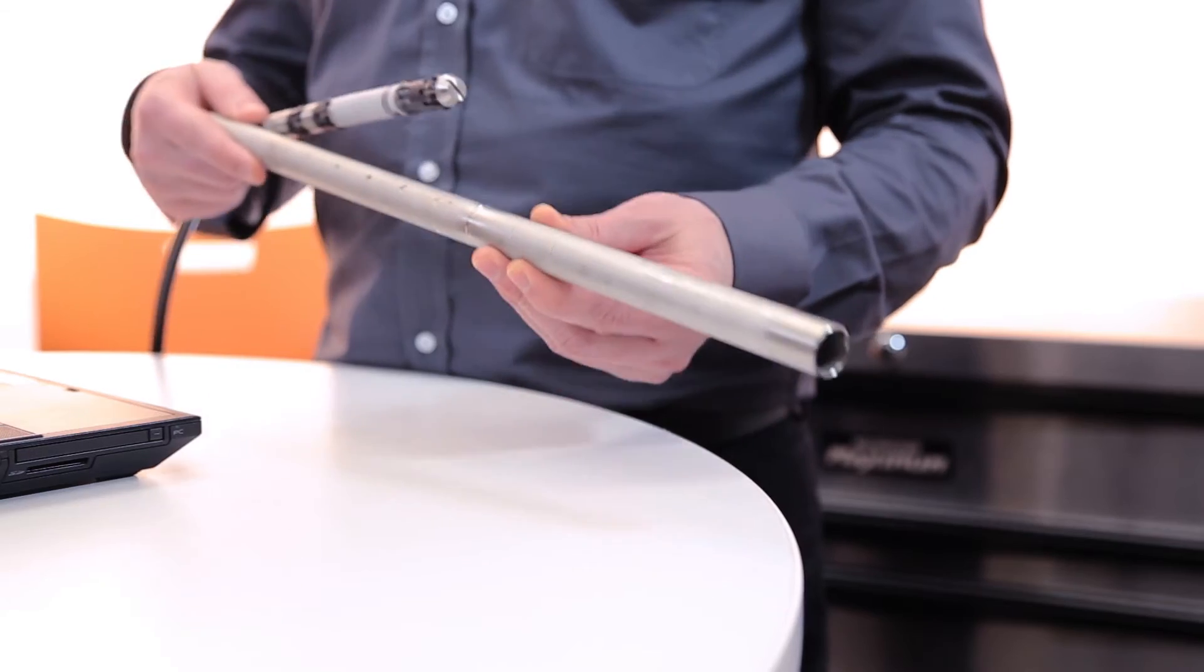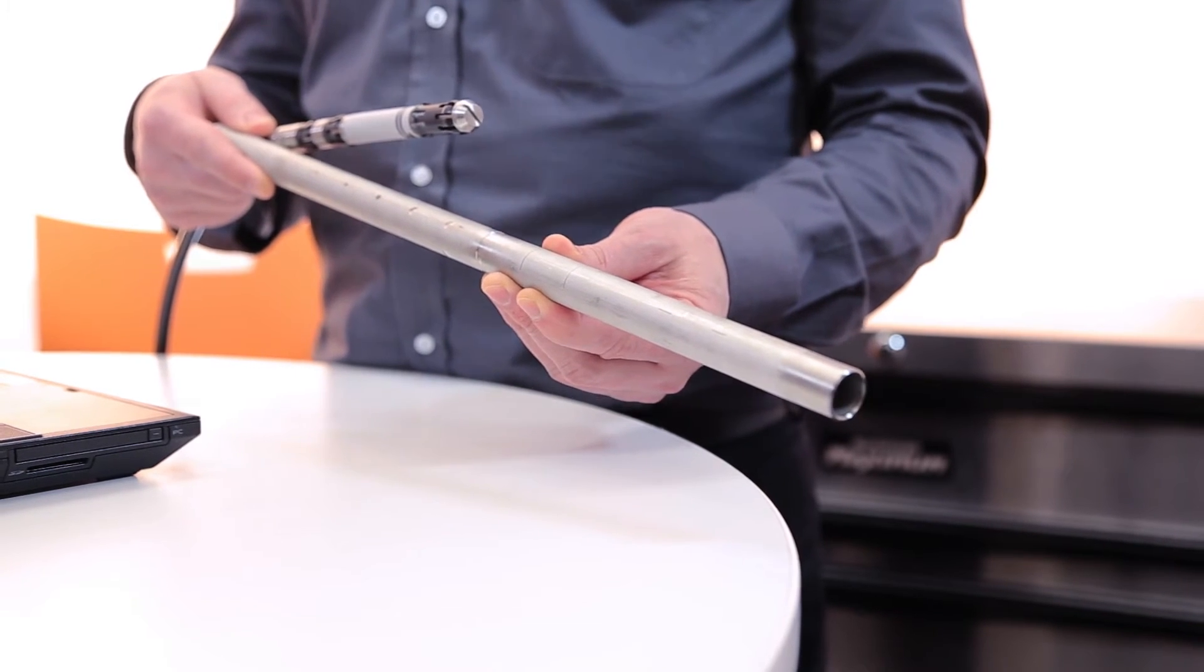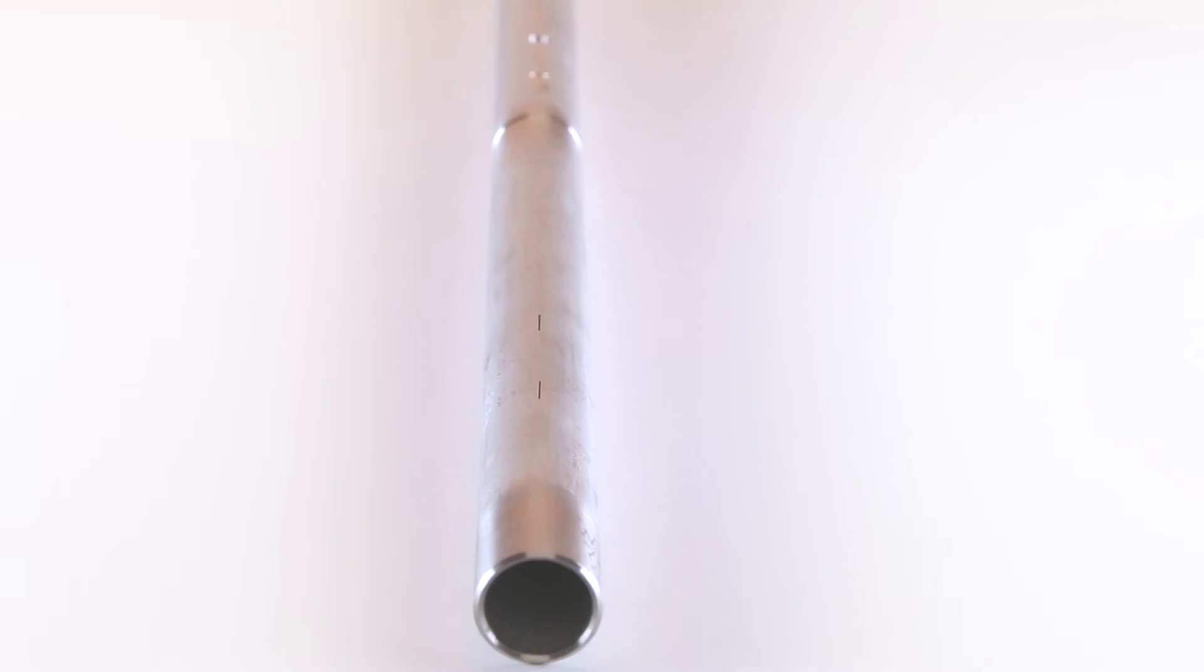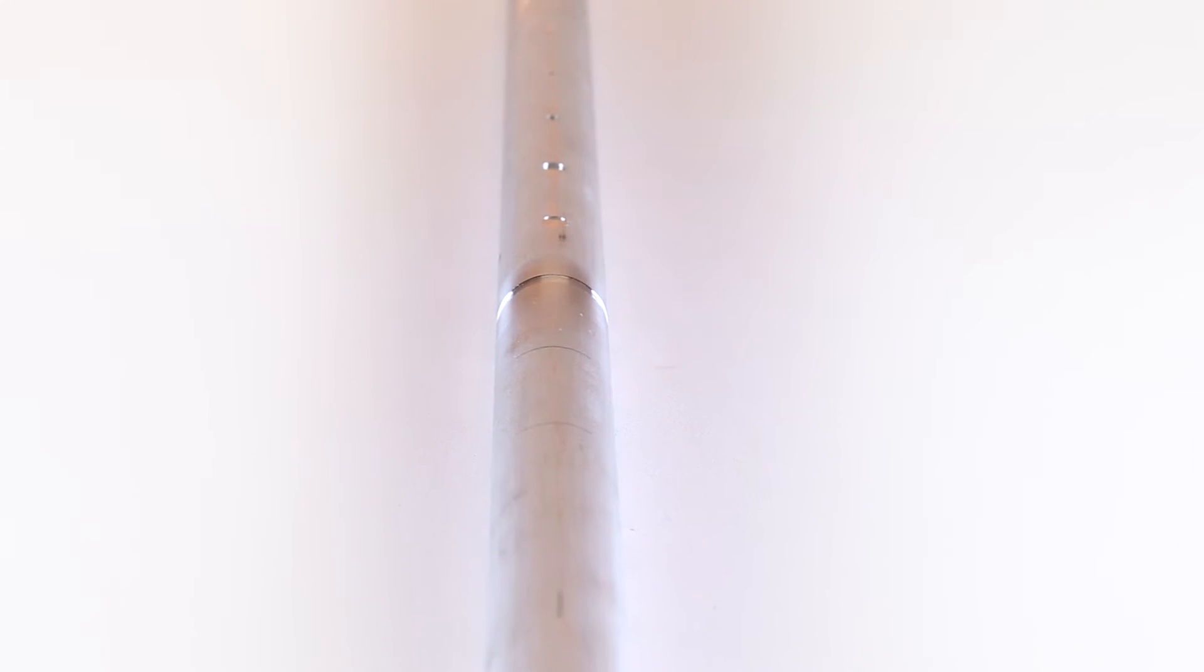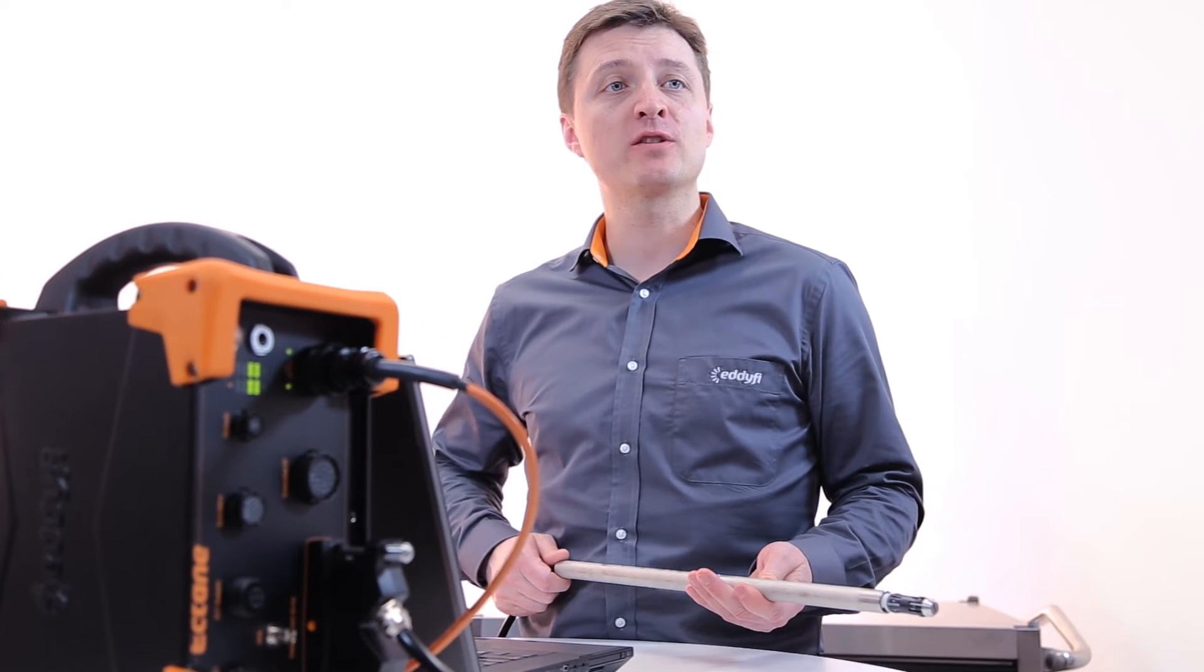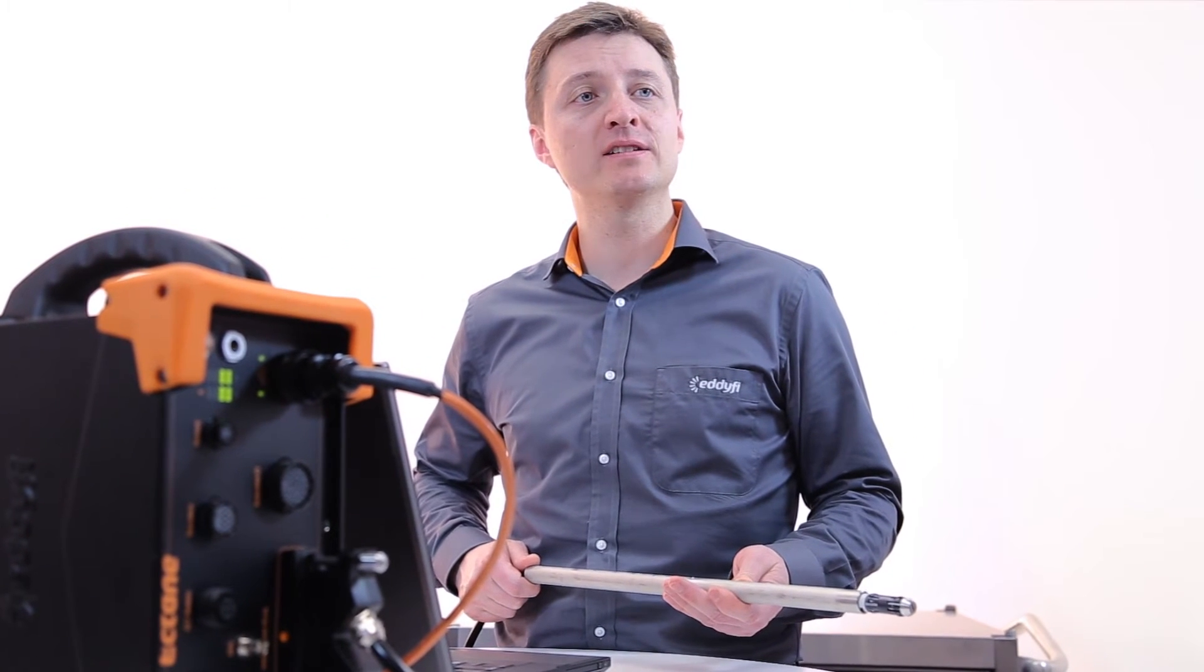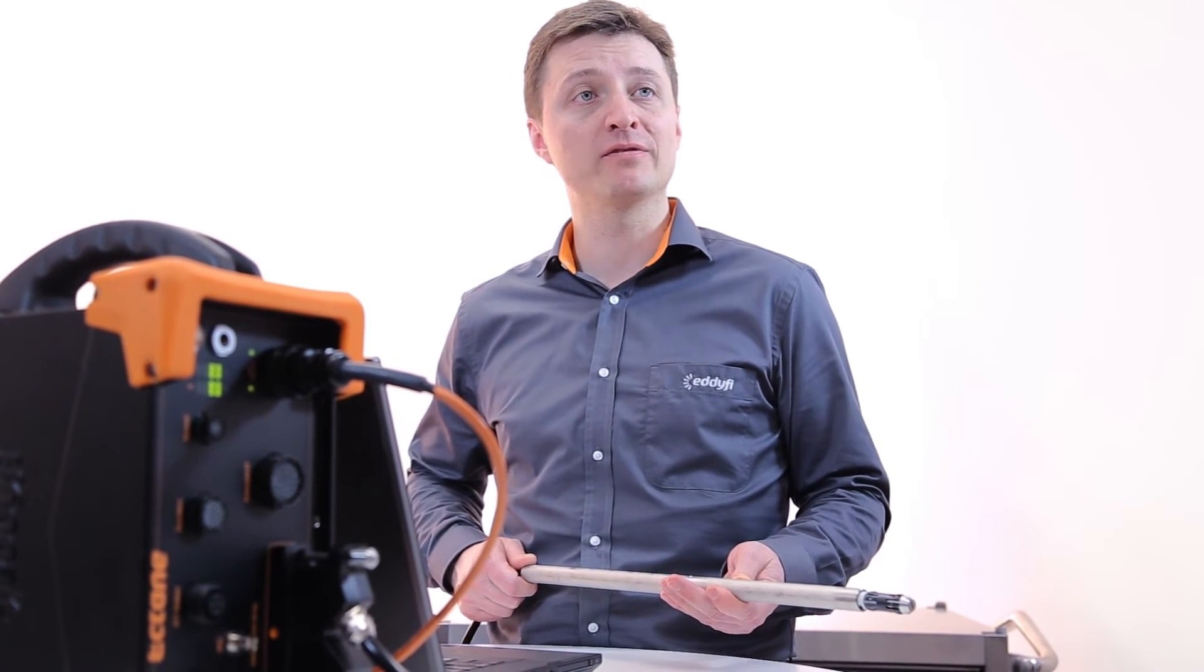To demonstrate the capabilities of the eddyfi probe, let's use this modified ASME calibration tube. The tube has a variety of simulated defects, including circumferential notches. First, let's perform an acquisition without any ferromagnetic interference to see what we can find.